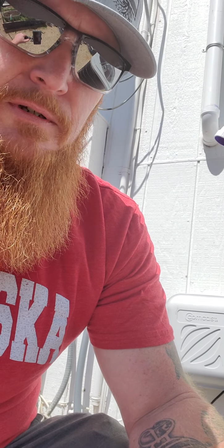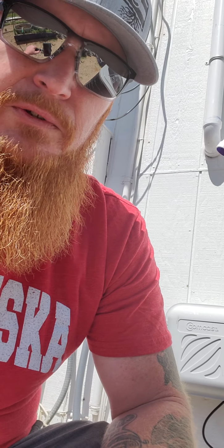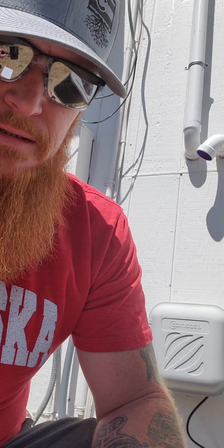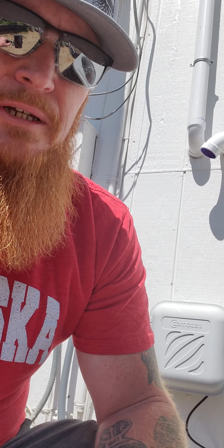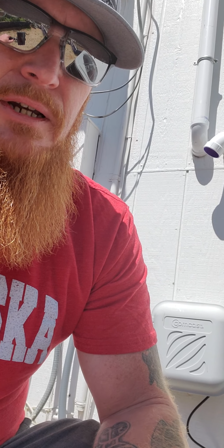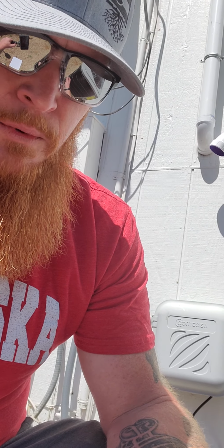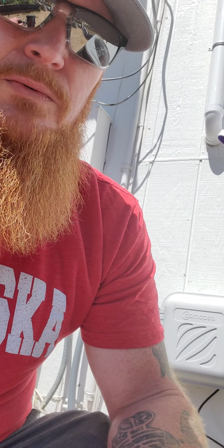filter first, and when you start doing ACs, the number one thing that you always check before you do anything is a filter. 9 chances out of 10, a dirty filter is actually what causes an AC to go down. So make sure that the filter's clean, so that way the bottom side of your coil isn't filthy. But the hot, moist air flows through your filter and then flows through your evap coil.